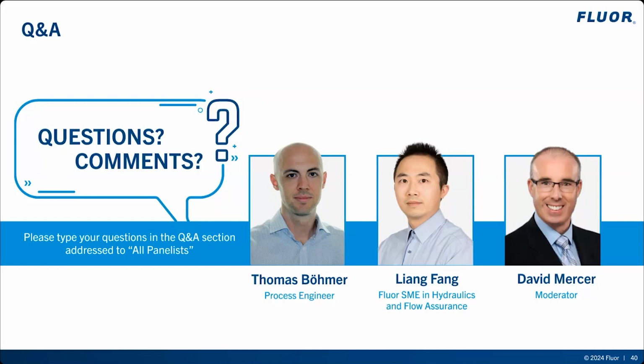Yeah, thanks for the question, Dave. This is quite a nice question to illustrate, let's say, the practical implications of surge screening. The line length doesn't affect the maximally achievable surge pressure, or rather the Joukowsky calculated surge pressure, and you'll also not see a length-related factor in this equation. But in short lines and in normal operation, conditions don't really change fast enough to create the Joukowsky head, which creates this misperception as to where the surge can happen.